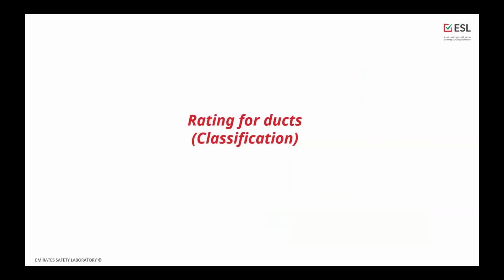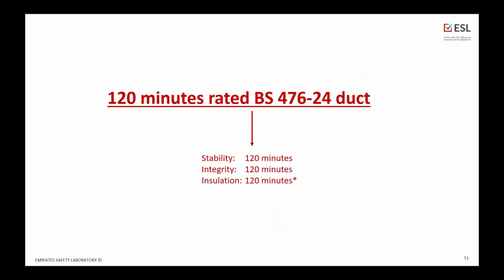In terms of the fire rating, for the BS, we have quite a simple rating. We have just the 120-minute rated BS 476 part 24 duct, which stands for stability, integrity, and insulation. However, insulation must be mentioned together with the rating, stating whether this is an insulated or uninsulated duct.